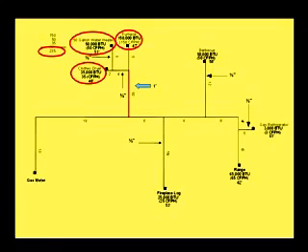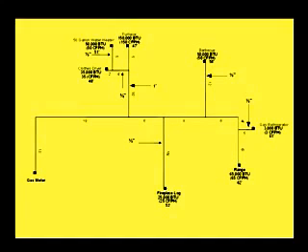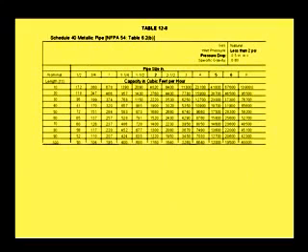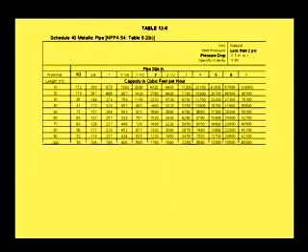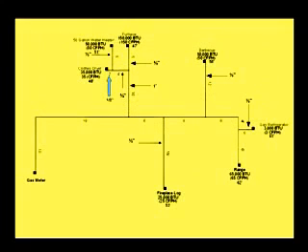Now that we have sized the branch main line, we can change rows based on the distance the last two appliances are from the meter. The 5-foot section supplying the furnace is 47 feet from the meter with a demand of 150 cubic feet per hour. Refer to table 12-8, 50-foot row — 150 fits under 151 — and see that a 3/4-inch pipe will accommodate the furnace. The 2-foot section for the clothes dryer is 48 feet from the meter and has a demand of 35 cubic feet per hour. Refer to table 12-8, 50-foot row — 35 will fit under 72 — and see that a 1/2-inch pipe will accommodate the 35 cubic feet per hour demand for the clothes dryer.